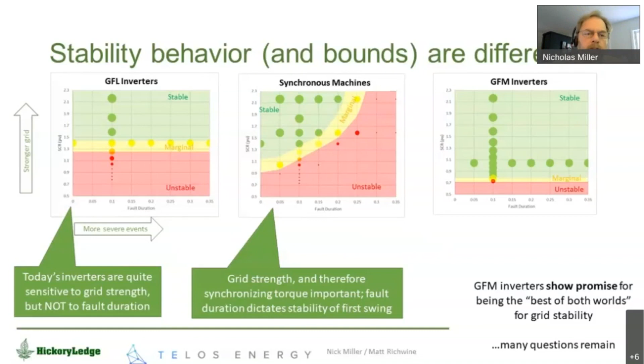There's a bunch of tools in your toolboxes that you're accustomed to that are intended to make the system more stable and give you the ability to push more power or handle more violent events. The industry has made grid-following inverters spectacularly more stable. The stuff being made by the big OEMs today can get you down into short circuit ratios below 2, which was almost impossible a few years ago. This trend is expected to continue, but there are some limitations on it.